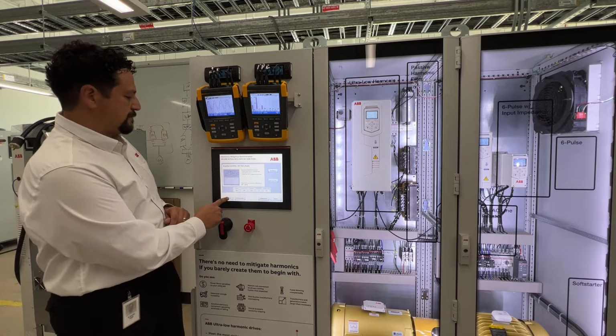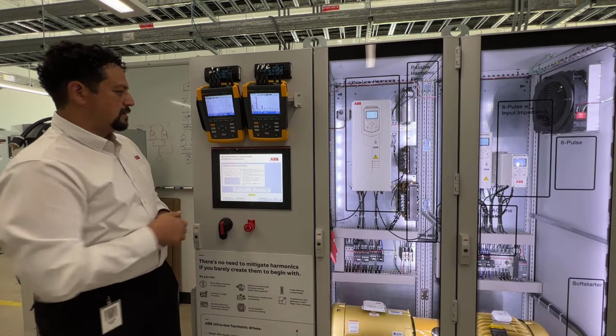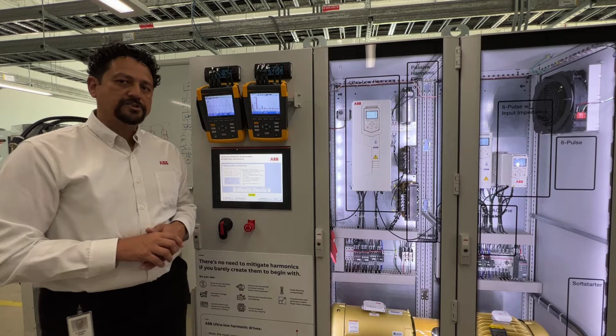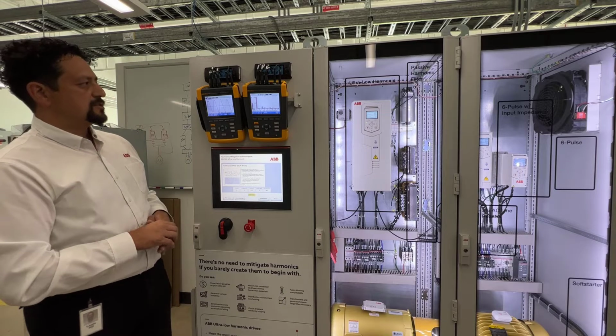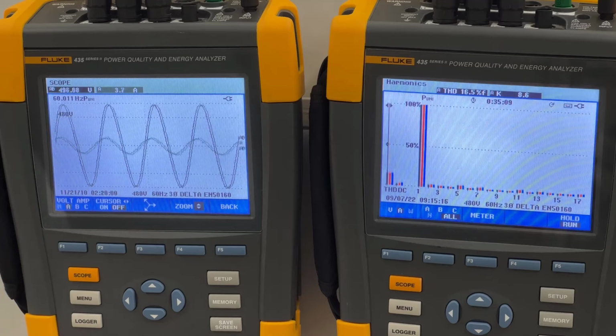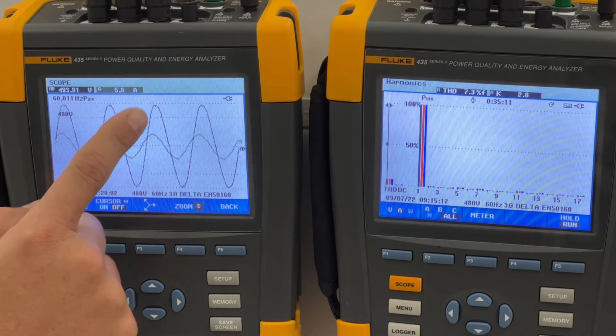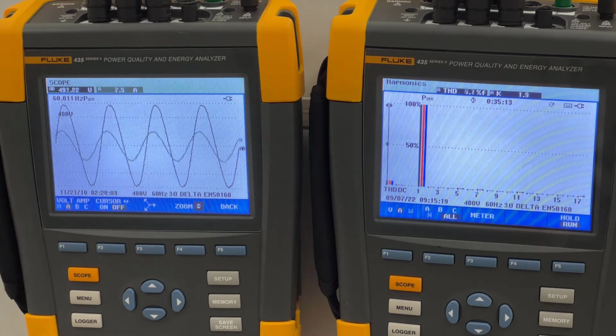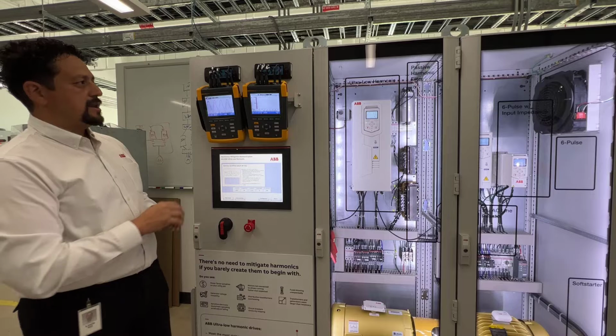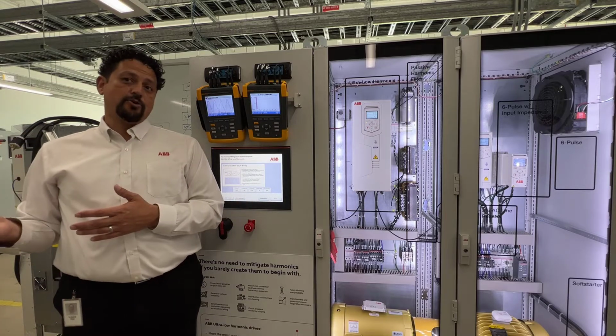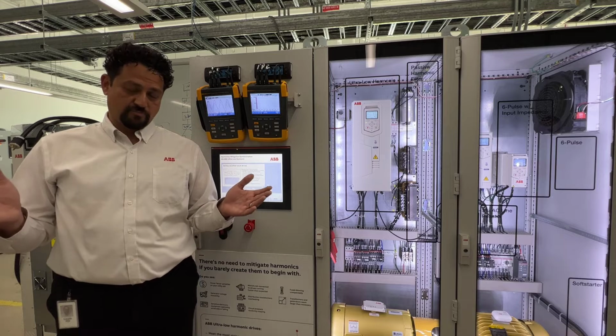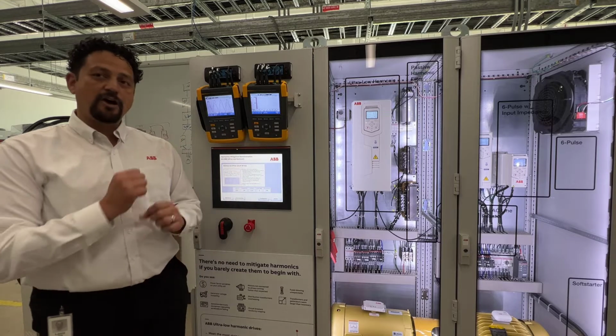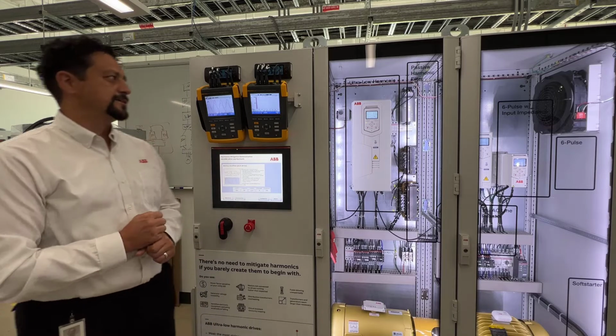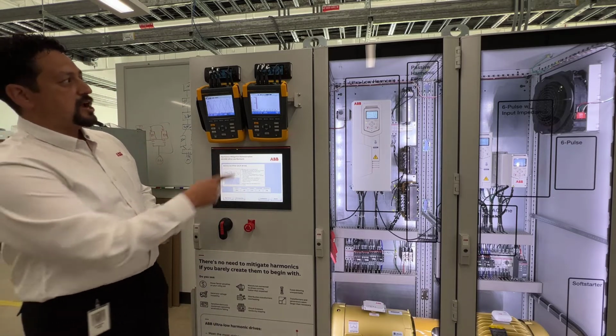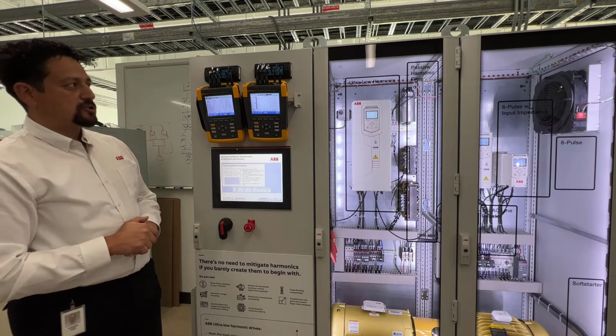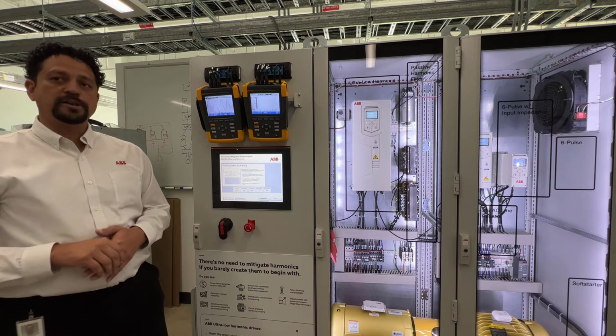But the best way to make this improvement is by applying our ultra-low harmonic technologies to your electrical system. As it comes up to speed, you can see that the waveform is almost purely sinusoidal. The pronounced bunny ears that we had are gone, and now it's no longer gulping. So let's go back to the horse analogy. Imagine, as weird as it may sound, giving the horse a straw. Now the horse is taking all the water that he wants, when he wants it, and we're doing the same thing here. You can see that our current distortion is 3% at our drive terminals, and that gives us the performance that we're looking for.